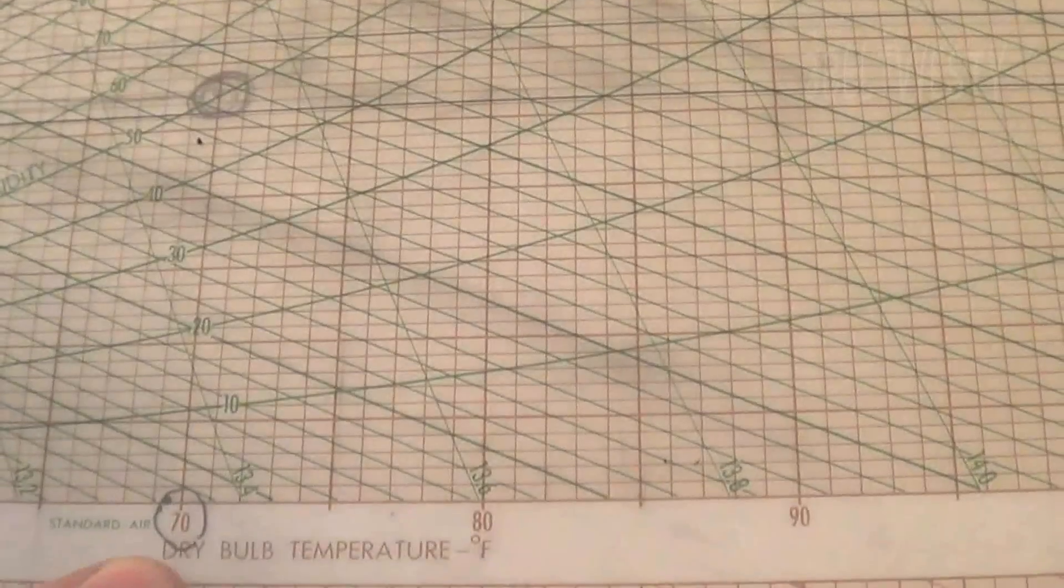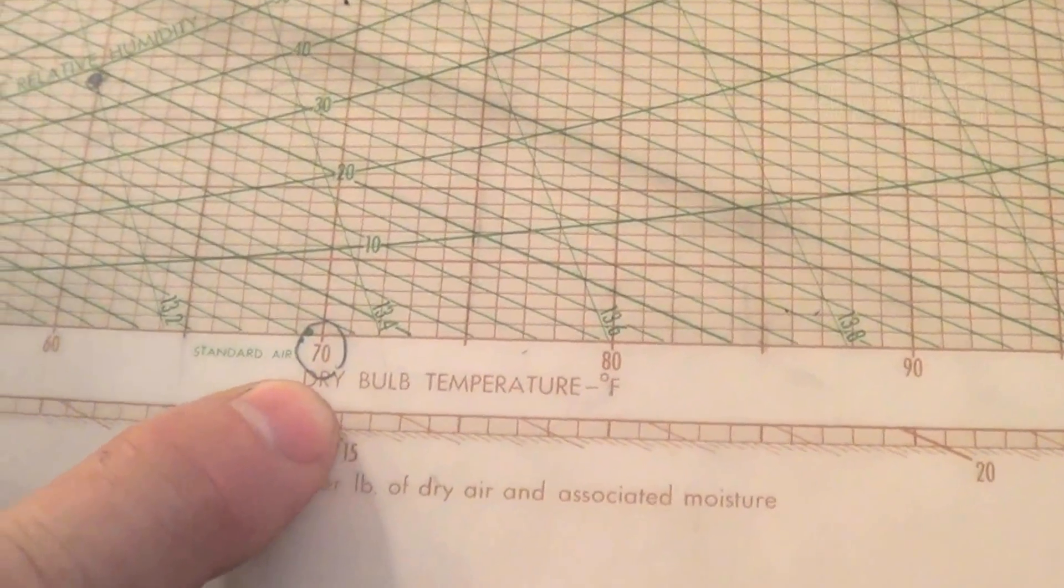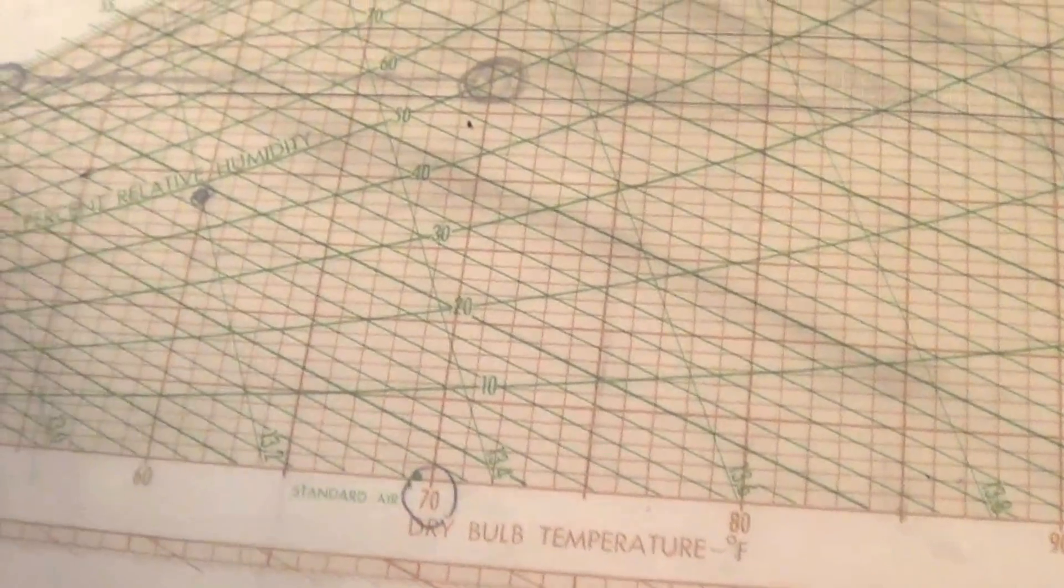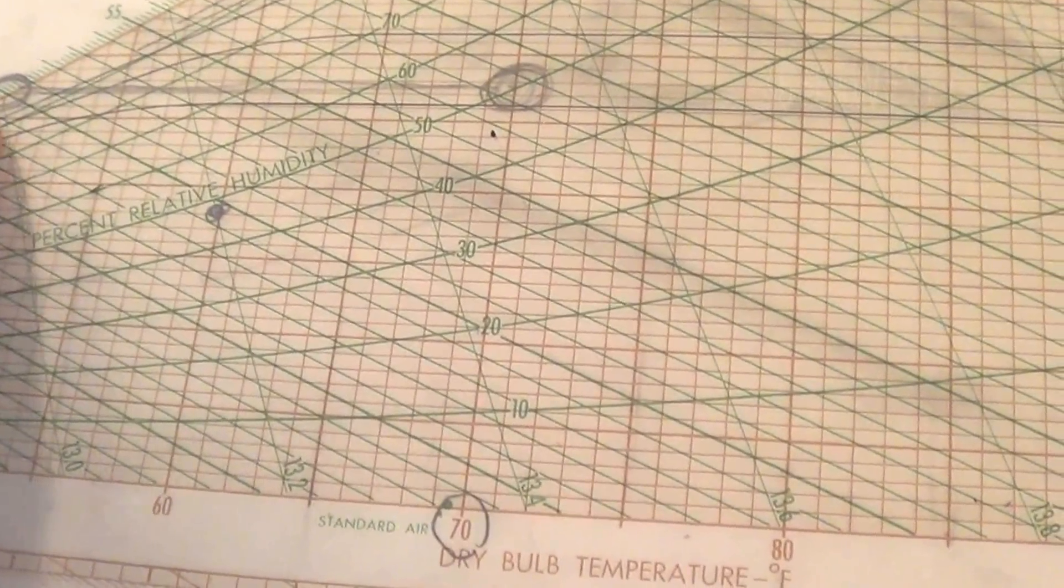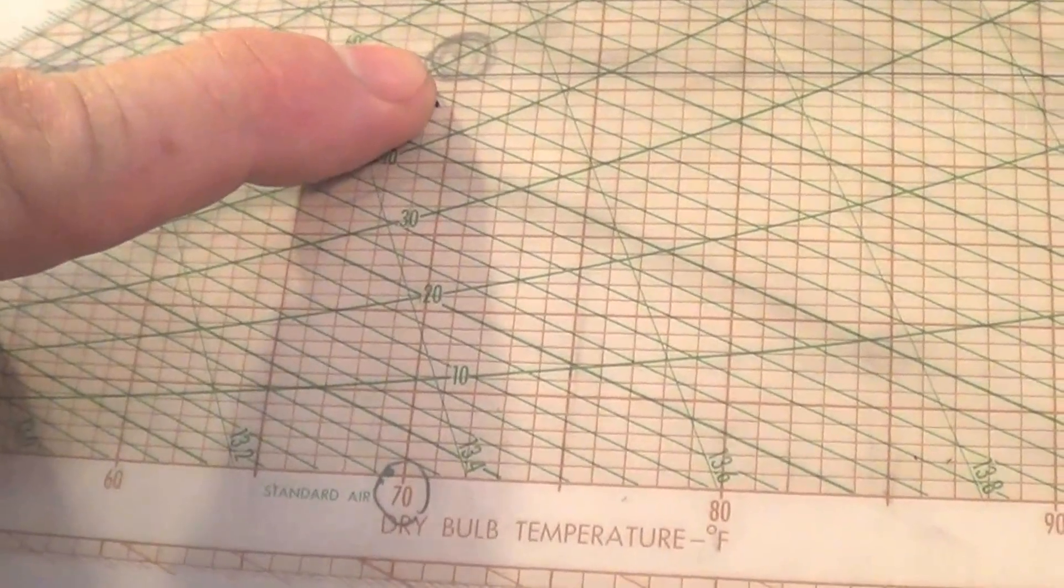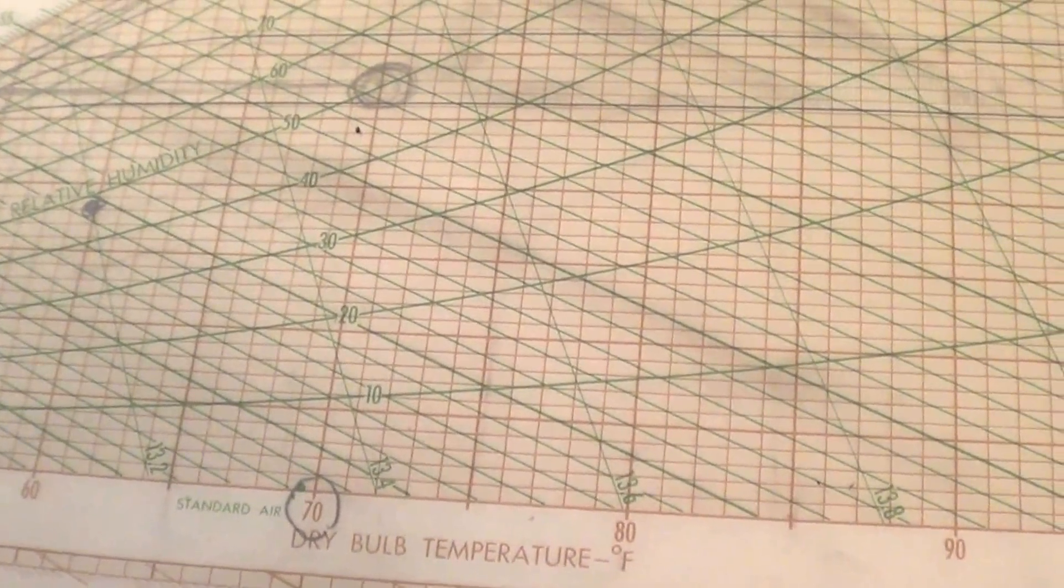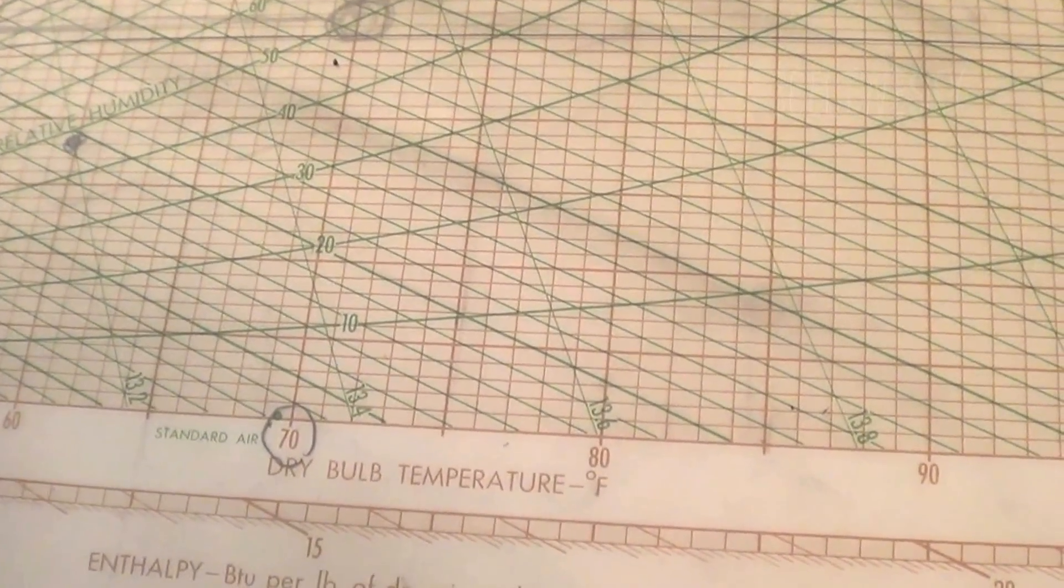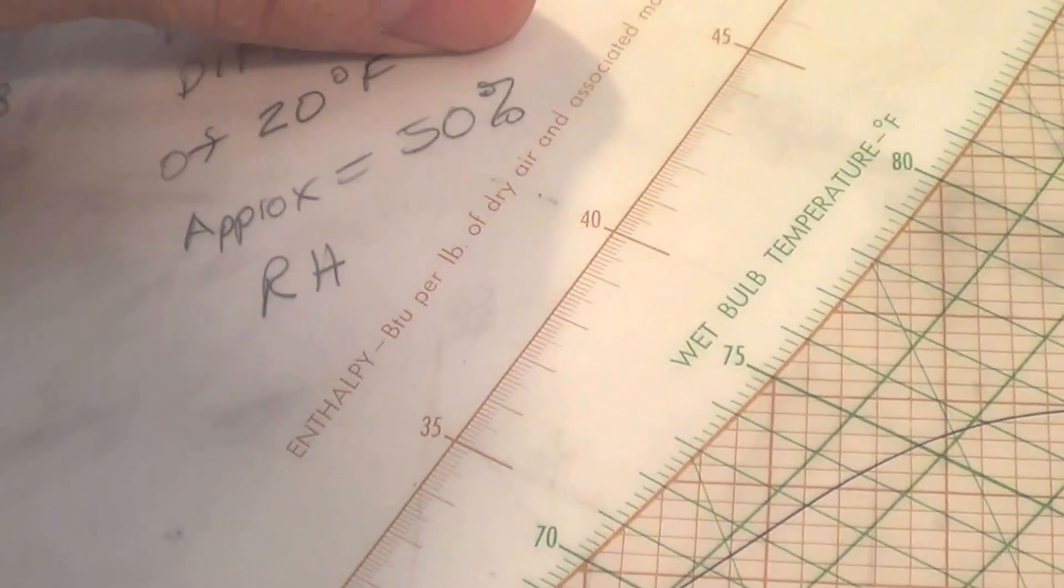If I go down here to a dry bulb temperature of 70 degrees and a dew point of 50, you intersect them, you've got 50% RH. Over a fairly decent range, if you have a 20 degree differential, you have roughly a 50% RH.